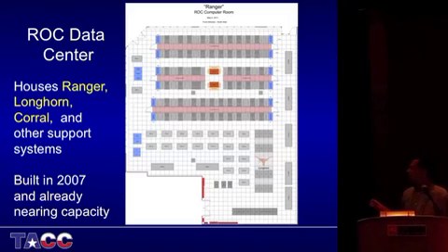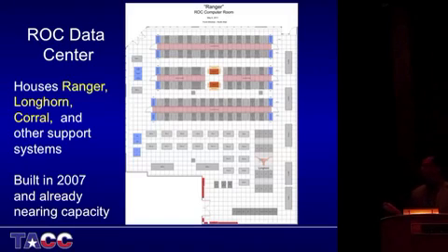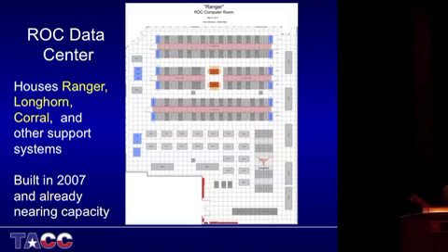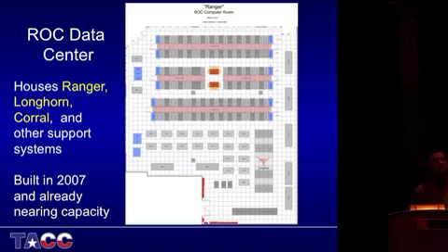Now, a couple things we didn't like in the original design for Ranger: each one of these gray boxes is actually a power distribution unit. We needed 1,400 20-amp circuits to run Ranger. To provide all of that circuit, you have to have tons of panel space. So there are 4 circuit breaker panels in each of these boxes, and 21 of these PDUs spread through the room.